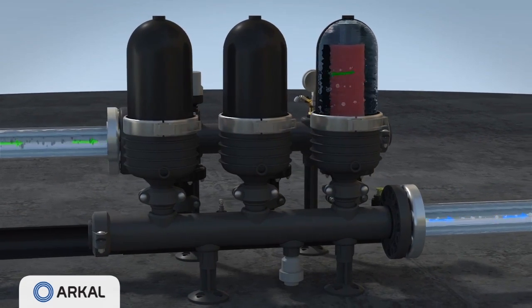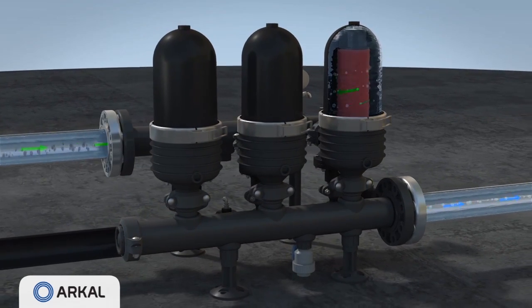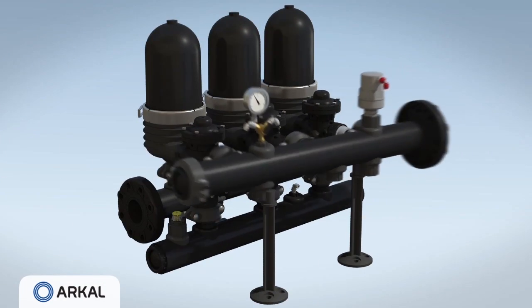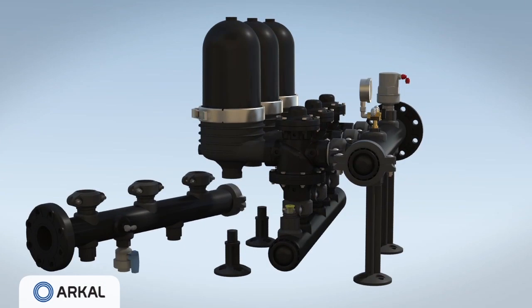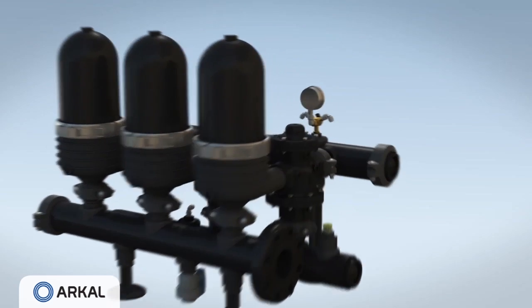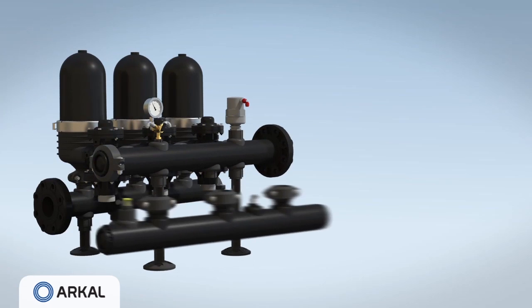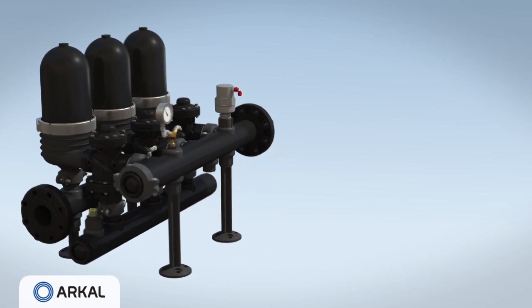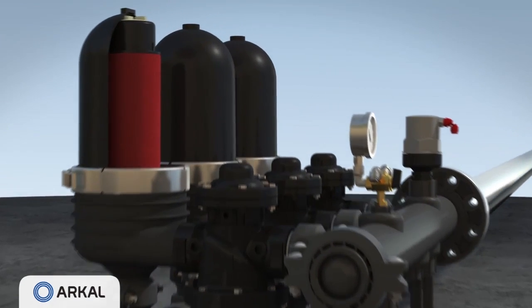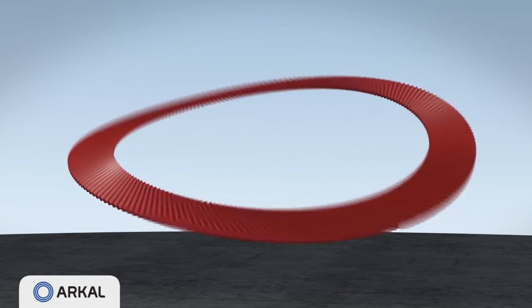The Spin Klin filters are highly suitable for corrosive water applications due to their polymeric construction. Spin Klin's system comprises an inlet and outlet manifolds, a given number of filter modules, three-way valves, a drain manifold, and a backwash controller. Each filter module consists of a filter housing with a central spine on which the Spin Klin discs are stacked.